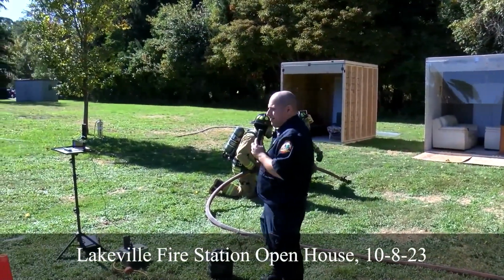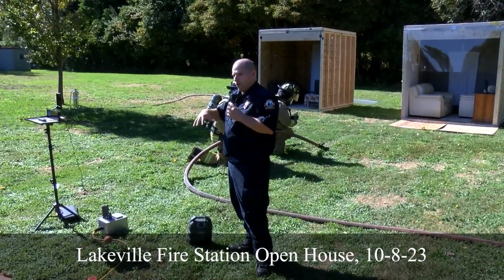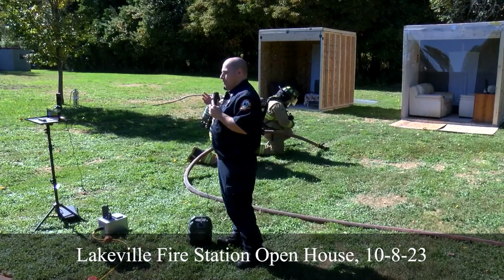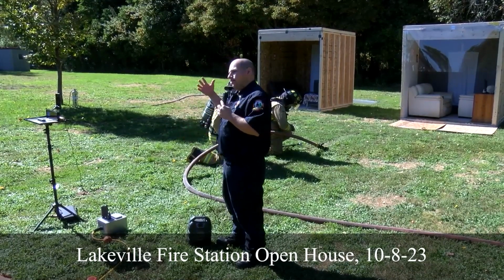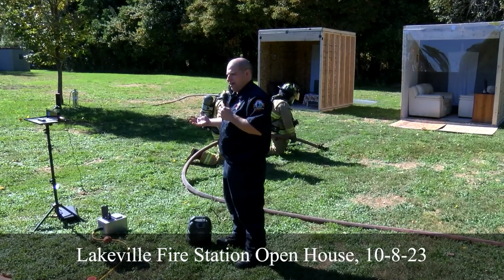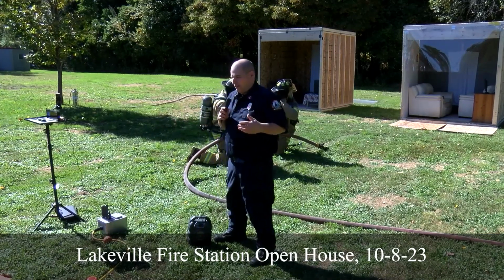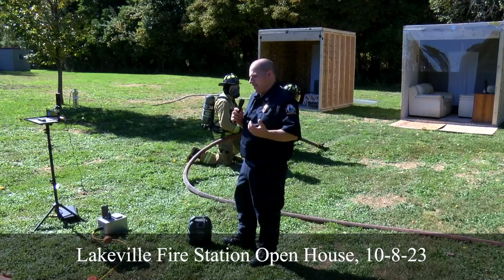So the way the sprinkler technology works now is home fire sprinklers are designed to work with your existing water supply. If you have water coming in from the town, that water supply is more than sufficient to run the home fire sprinklers. If you have a well, your well capacity might be able to do it. You may have to upgrade your pump if you're renovating, or if you're in an area where you have shallow wells or something that's not going to be able to meet the water supply standard. You can also install just a small cistern that will supply these.